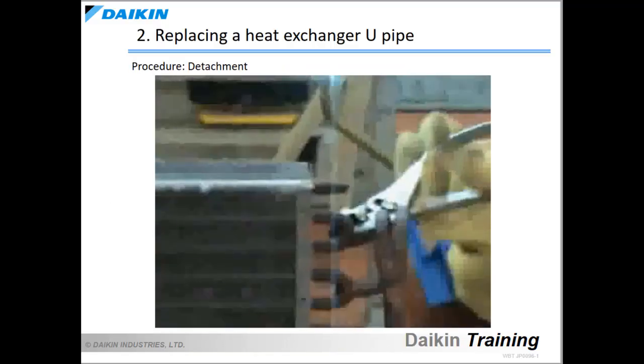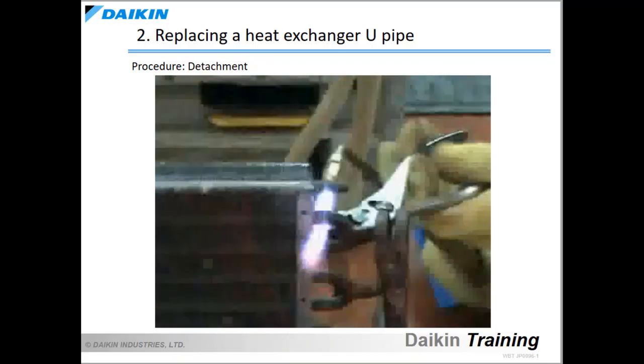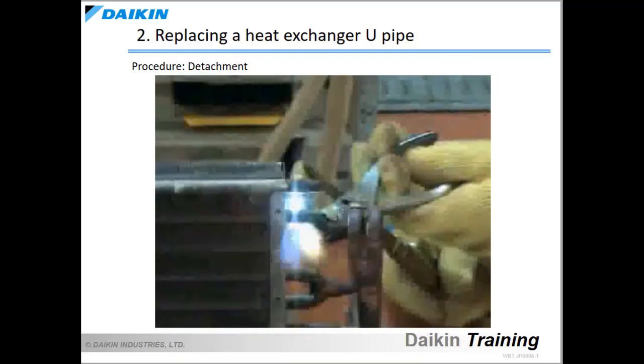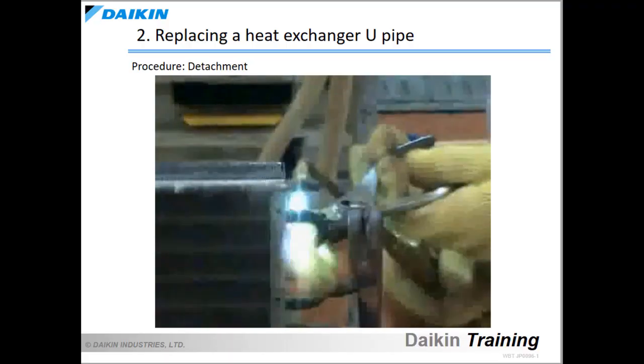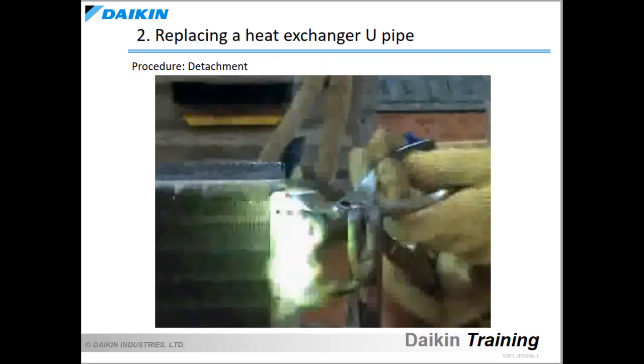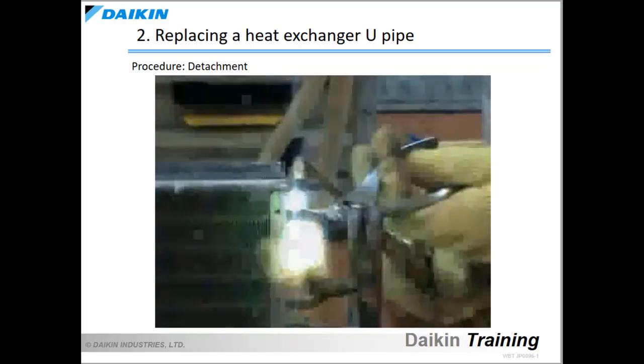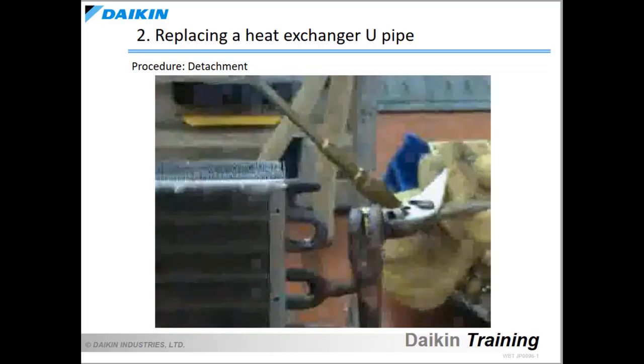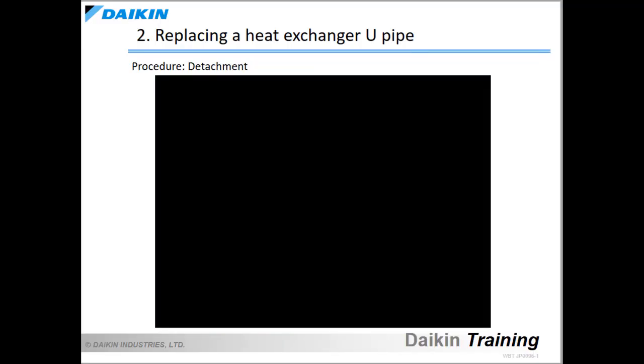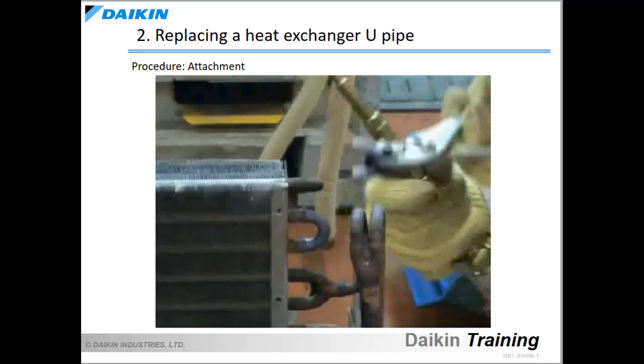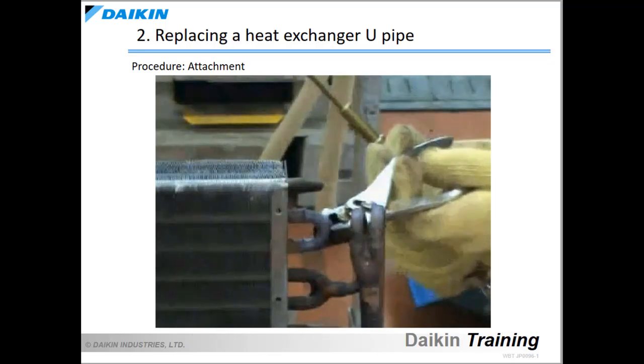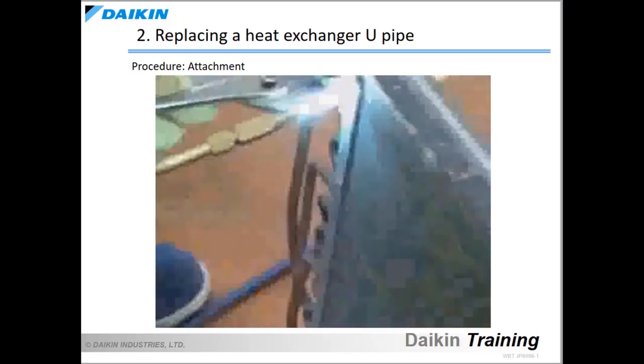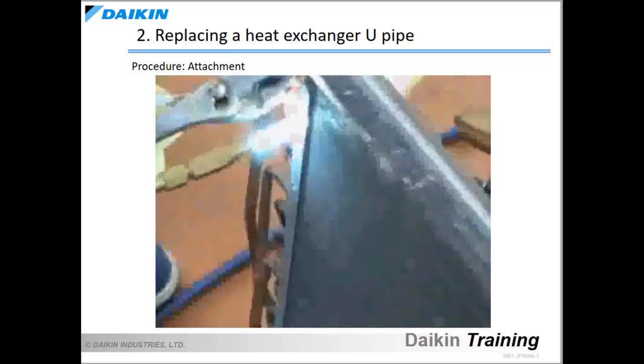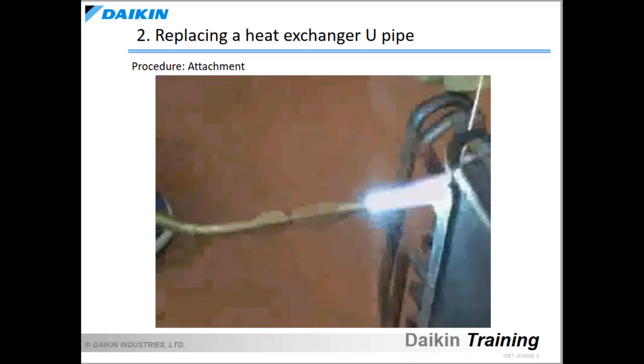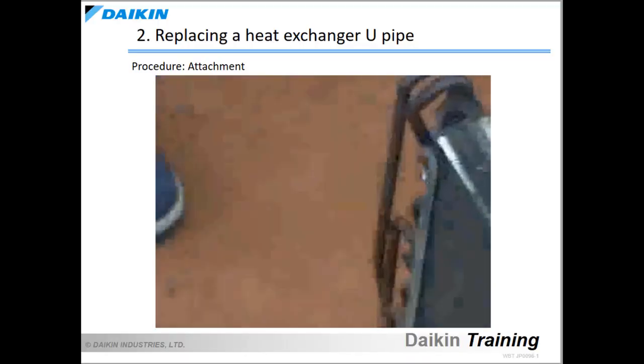Let's review the procedures for replacing the U-pipe in the video. Light the torch and adjust the flame. Use the reducing flame. Adjust the flame to a low intensity. Hold the U-pipe with pliers and detach it by alternately heating the two connection areas on the U-pipe with the flame. When attaching the U-pipe, hold it with pliers, insert it lightly into the joints, alternately heat the two connection areas, and then firmly insert it all the way in the joints. After the U-pipe is inserted, distribute the brazing filler metal from behind the joints.